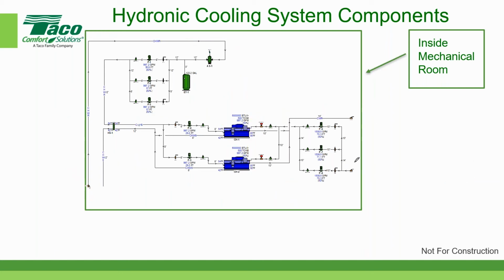So all of this stuff in this little box is inside the mechanical room. This is what you typically find inside a mechanical room for a hydronic cooling system, also known as a chilled water system. Let's emphasize a couple of things. We're sending water out to the cooling towers in this direction, going out at 95 degrees Fahrenheit. The cooling tower is responsible for rejecting all of the heat from the building. Can I make an F over here? Yes, I can. Look at that, Brett. Yep, that's it. And then it comes back from the cooling tower at 85 degrees. The cooling tower is responsible for rejecting the heat in the building, but also the heat generated by the chillers themselves. So all of that's going out there.